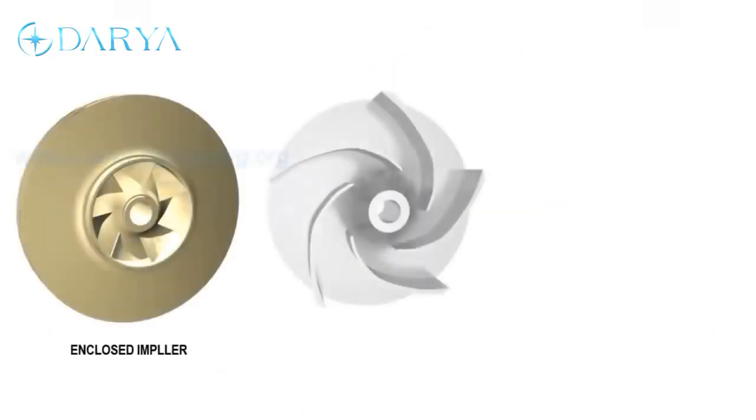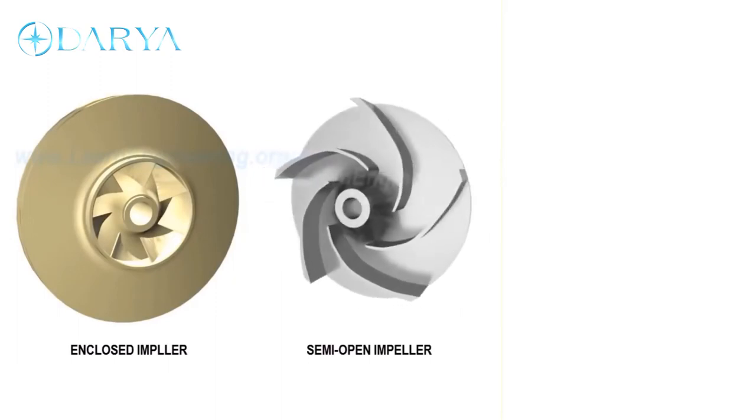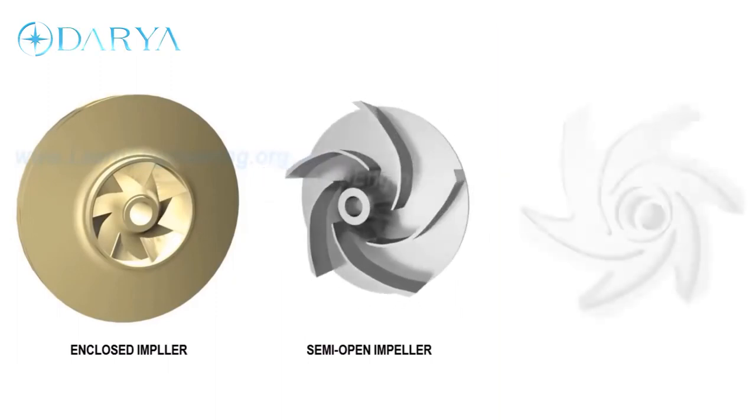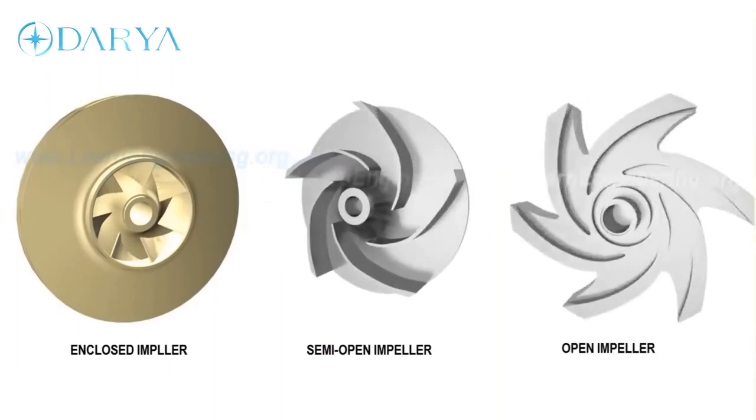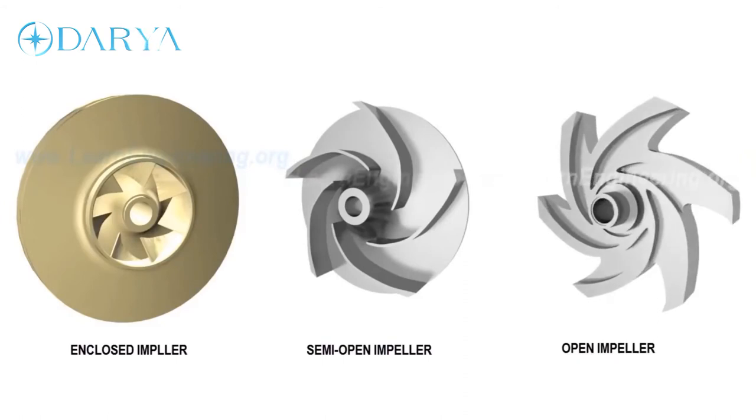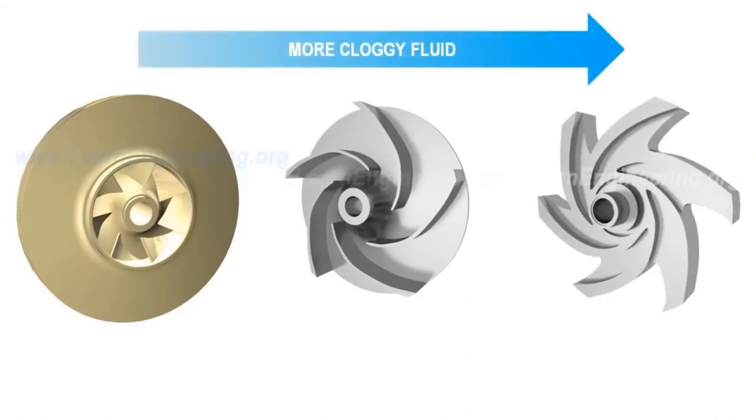Current impeller type is enclosed. Semi-open and open impellers are also in use depending upon application. If the working fluid is cloggy in nature, it is preferred to use open kind of impeller. But they are slightly less efficient.